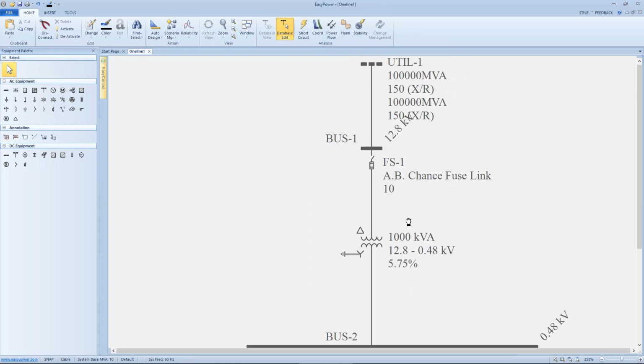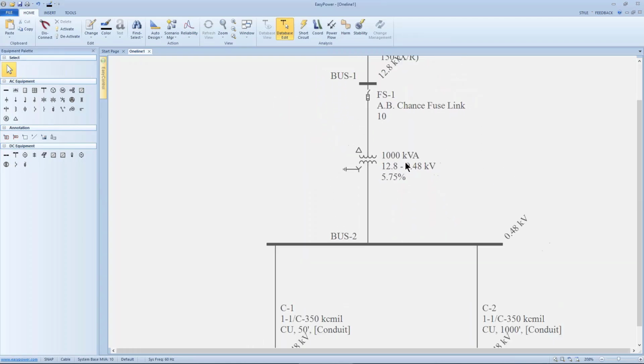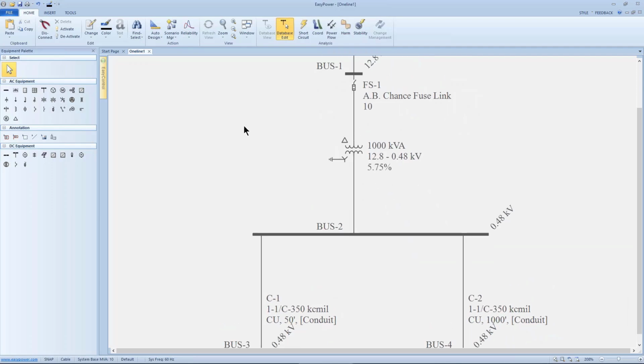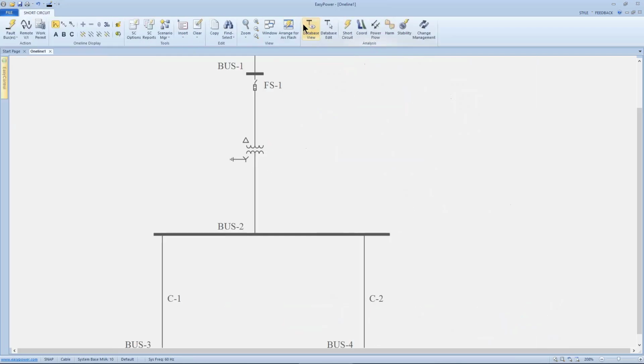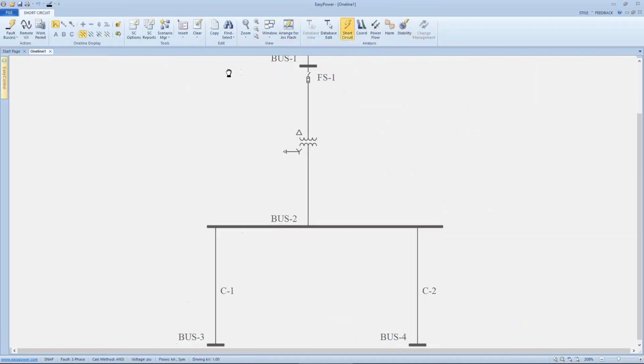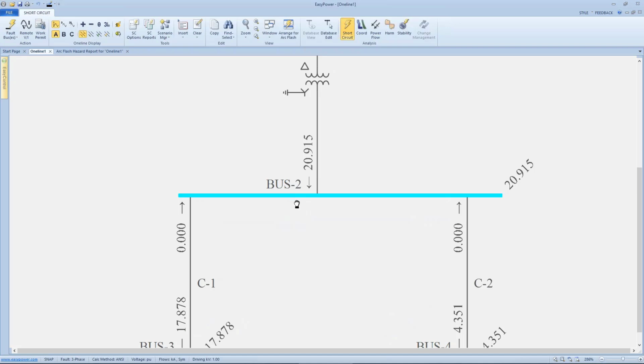So at that point, the electrician says, okay, I'm ready to calculate my short circuit current, so we go to short circuit focus, the lightning bolt at the top center of the screen. I get a new series of icons across my focus banner. He says the first thing we want to look at is half cycle current for a bolted three-phase fault. I'm up at the left-hand corner showing a balanced fault as the type of fault we're going to use, and we're going to apply the lightning bolt on the far left where we fault all the buses. And at that point we get some numbers and some pretty colors.